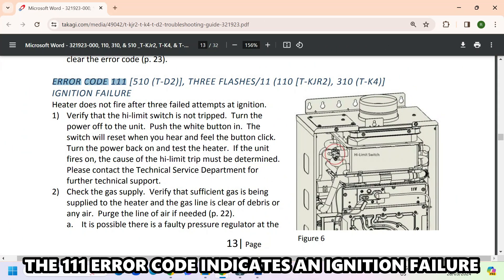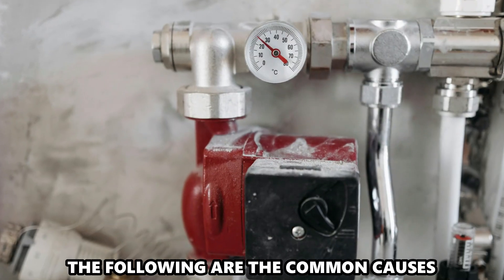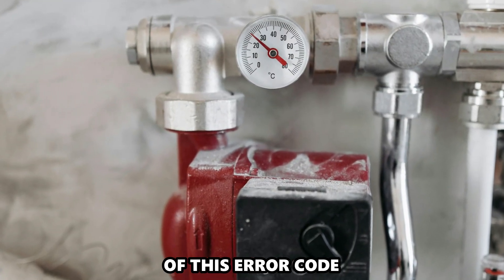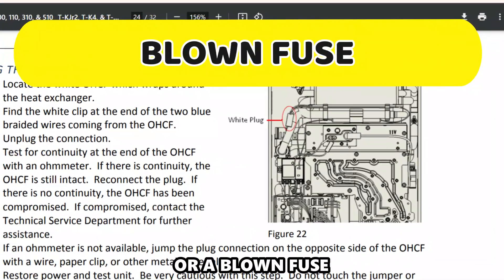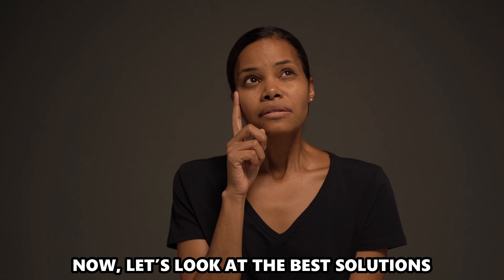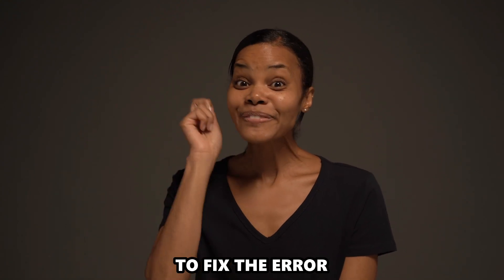The 111 Error Code indicates an ignition failure. The following are the common causes of this Error Code: low gas supply, a damaged igniter, or a blown fuse. Now, let's look at the best solutions to fix the error.